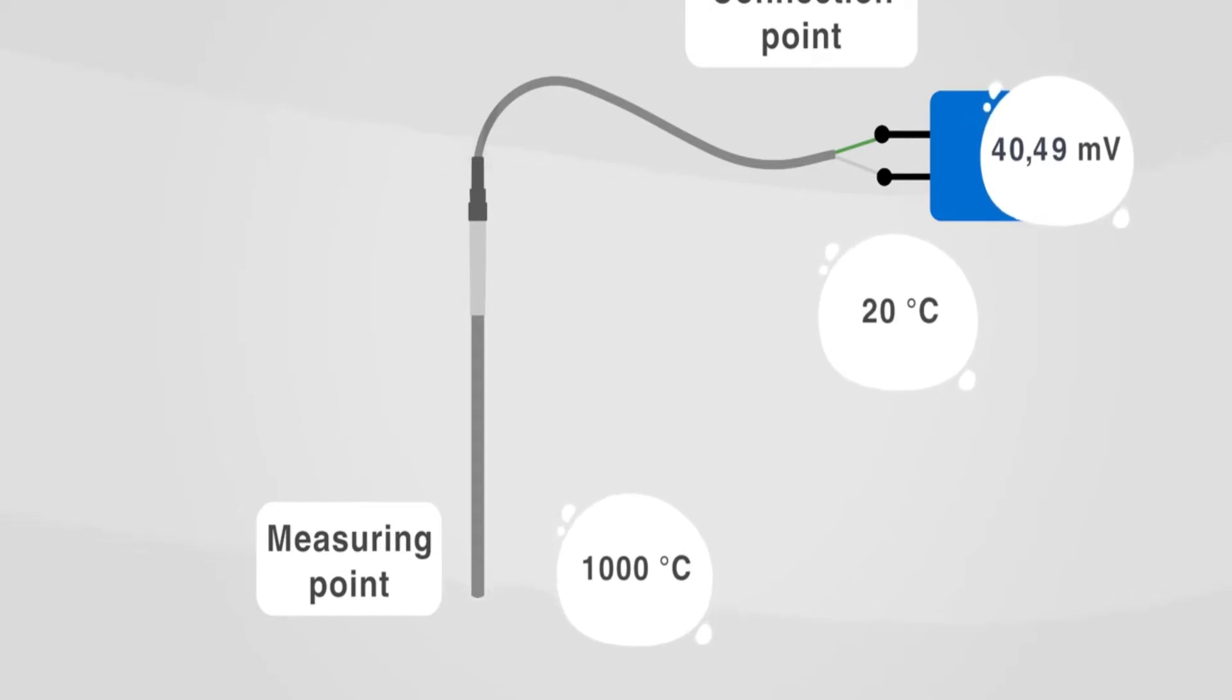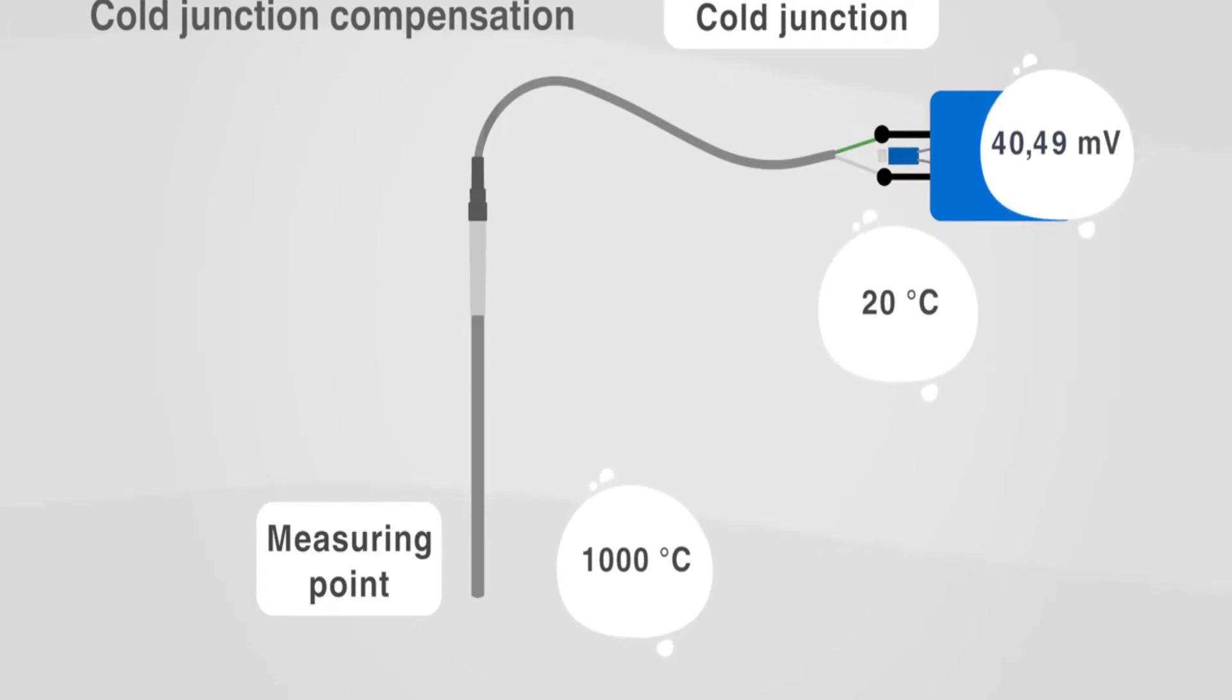For thermocouples, a cold junction compensation is necessary to ensure that the ambient temperature at the connection terminals of the cold junction does not affect the measuring result.